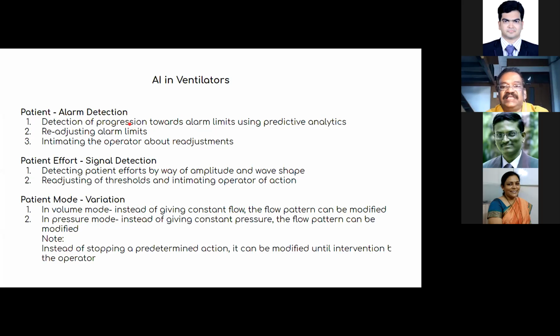And once that is detected, the instrument on its own can take an intelligent decision, or it can look at the cloud and compare the data in the cloud and take an intelligent decision for readjusting the alarm limits. But then it has to intimate the operator, could be a nurse or a doctor, about the readjustments. See, a ventilator is a very critical instrument, and to be very frank with you, if the settings are wrong, instead of helping the patient, you will kill the patient.